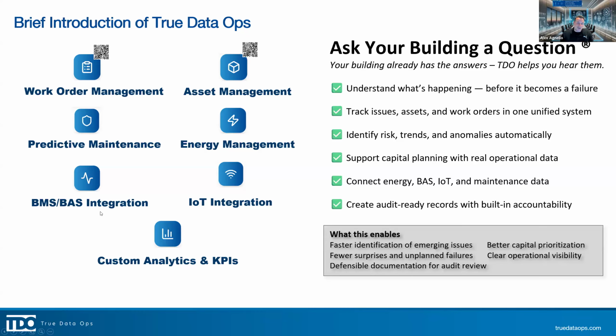This is with the BMS and BAS integration. If there's a VFD hooked up to this pump, which chances are it is, if it speaks BACnet or something else non-proprietary, we'll pull that information in addition. So now we can look at the VFD speed to see how fast it's running and the power it's using for vibration. We have a nice set of crosshairs on it. If we're looking at a pump curve—getting really techie here—we can see where that pump curve adjusts with the VFD and vibration. We can tell you a lot about it, and we'll actually schedule preventive maintenance against that pump for when you should do it.